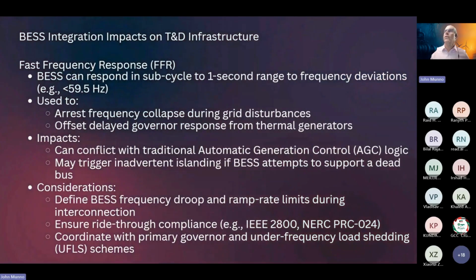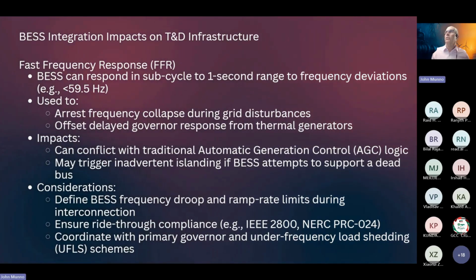So what else is there? Fast frequency response. These batteries can come on in less than a cycle or a 1 second range, and our grid protection may not be ready for that. We may have grid protection that's looking for a little bit longer trigger before we shut down whatever's causing the problem. So with this quick on-off ability of the batteries, we may end up inadvertently islanding or shutting in some of these BESS systems. So what do we need to do? We need to determine what the BESS frequency, droop, and ramp rate limits are during that interconnection study, and make sure that we can have ride through if it's safe for our equipment.